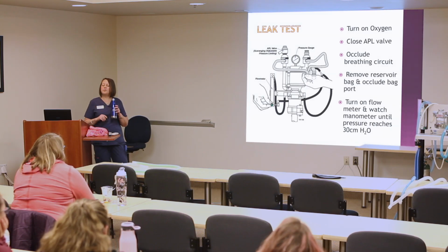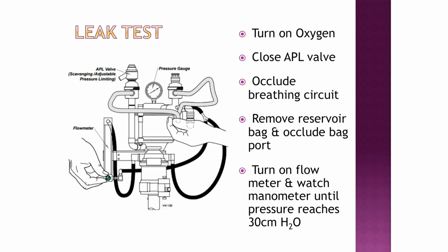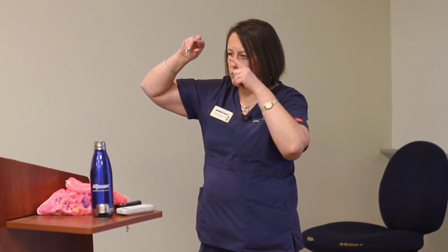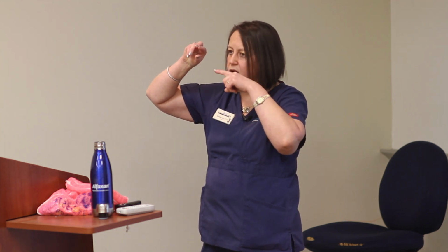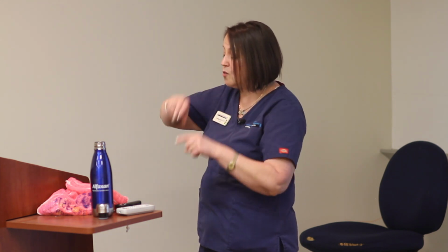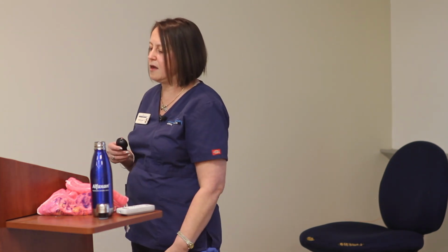So to do a leak test, I completely disagree with this picture because technically even the bags can have a hole in it. I'll show you guys how to do a leak test with the F circuit, and I do use a bag. You want to pressurize the circuit and then watch for the needle moving. And I can actually even see how big my leak is by turning up the oxygen flow until my needle stays without moving, without dropping down. And then I can look and see, is that a 200 milliliter leak or is that a 1 liter leak? Because if it's a 1 liter leak, you wouldn't want to use that machine. You want to find that leak.